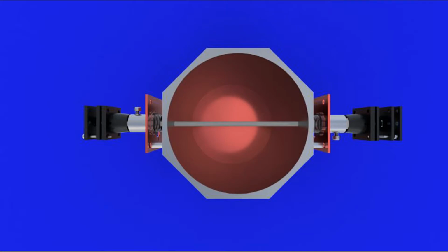To measure smoke, the best method is to have a light source and a sensor. You pass the light beam through your media, and the light that doesn't hit the sensor is your opacity measurement. The light that makes it through is your transmitted measurement.